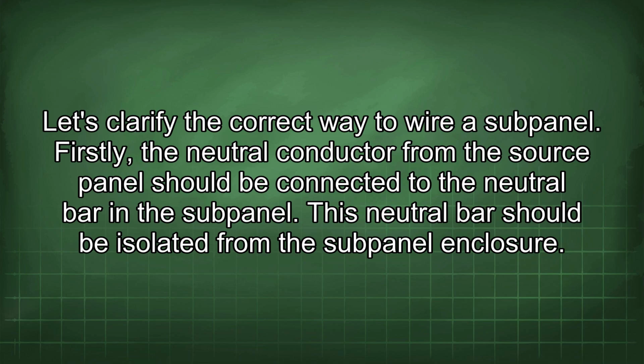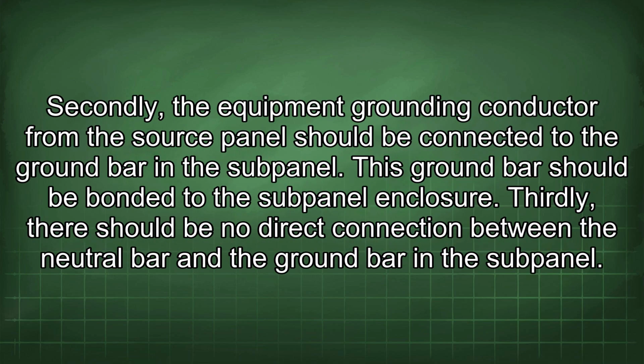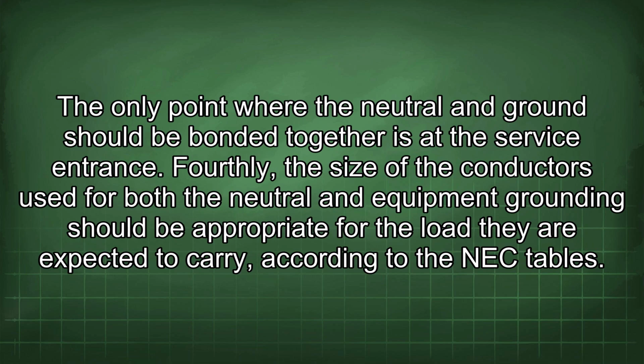Let's clarify the correct way to wire your subpanel. Firstly, the neutral conductor from the source panel should be connected to the neutral bar in the subpanel. This neutral bar should be isolated from the subpanel enclosure. Secondly, the equipment grounding conductor from the source panel should be connected to the ground bar in the subpanel. This ground bar should be bonded to the subpanel enclosure. Thirdly, there should be no direct connection between the neutral bar and the ground bar in the subpanel. The only point where the neutral and ground should be bonded together is at the service entrance.